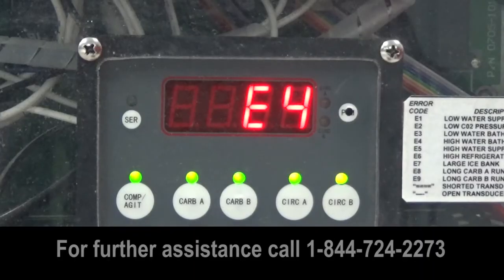If the compressor still doesn't start, check power from the control board going to the compressor. The issue could be a bad control board, broken wire, bad contactor, or a failed compressor.